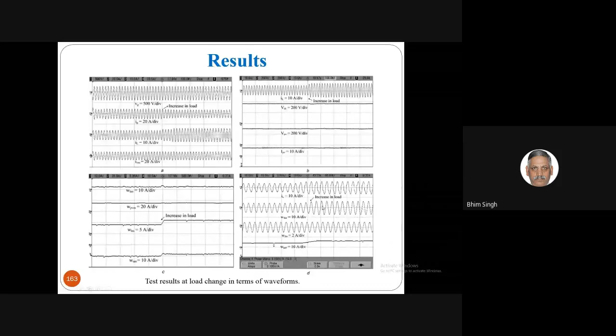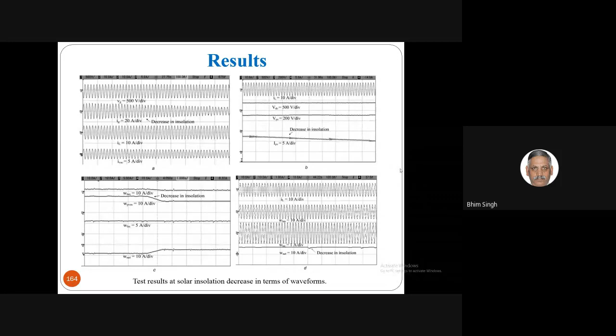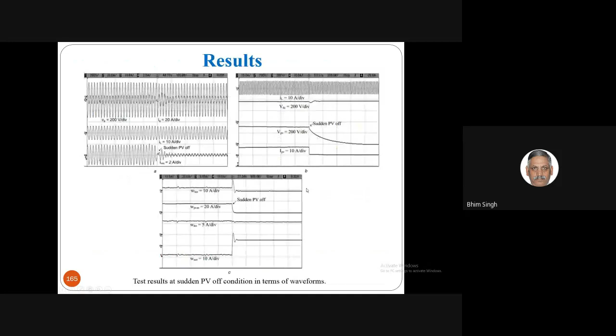Even when the grid voltage is changing, the load is changing, and the solar panel PV power generation is changing, the system runs without disturbance under all conditions. Of course, we have to honor the rating. So even if the PV is off, it works as a D-STATCOM, maintaining the grid current in phase with the voltage, whether or not power generation is there.